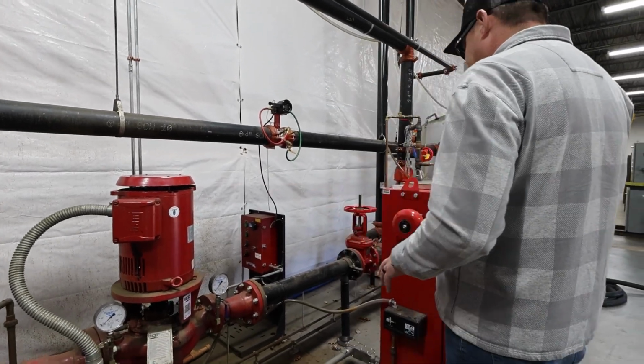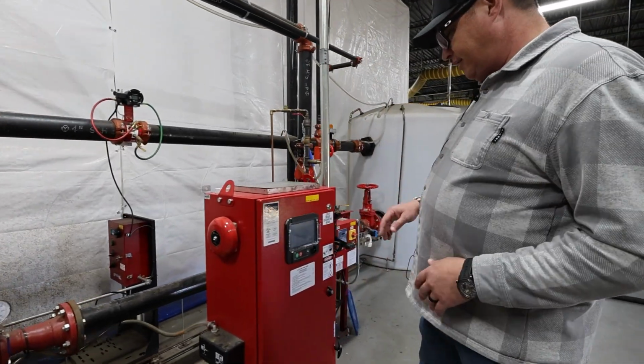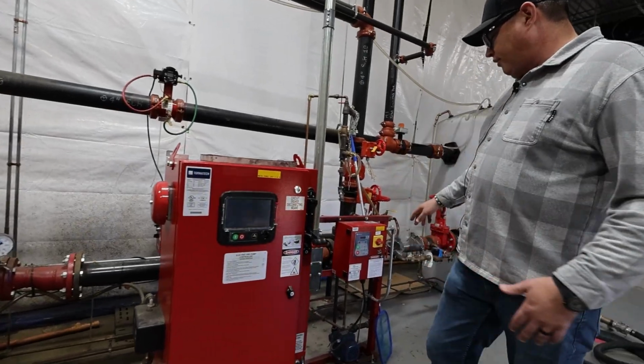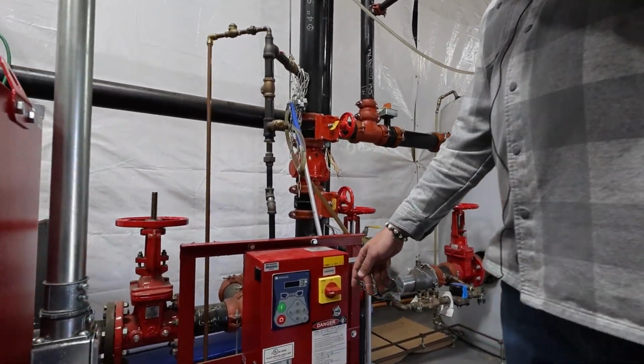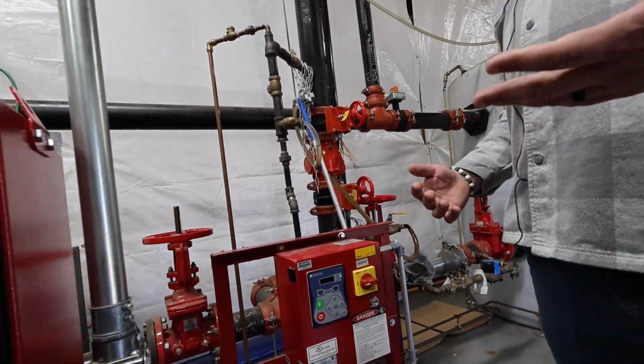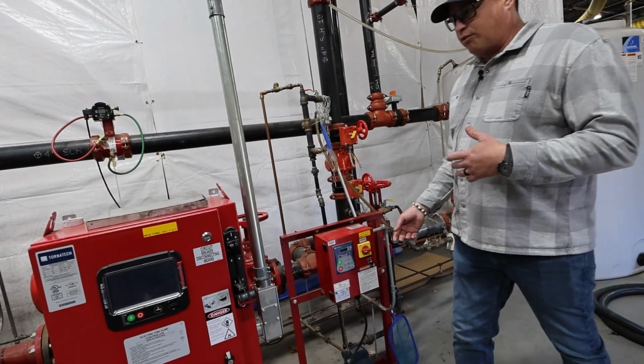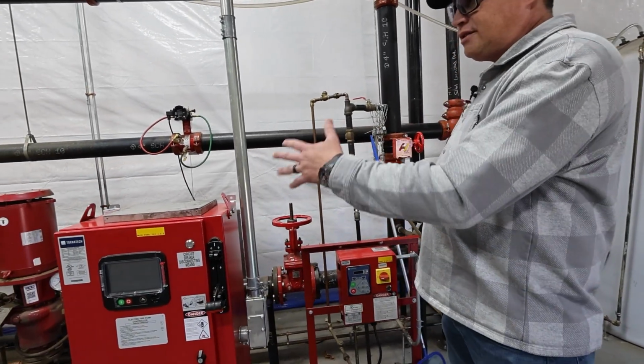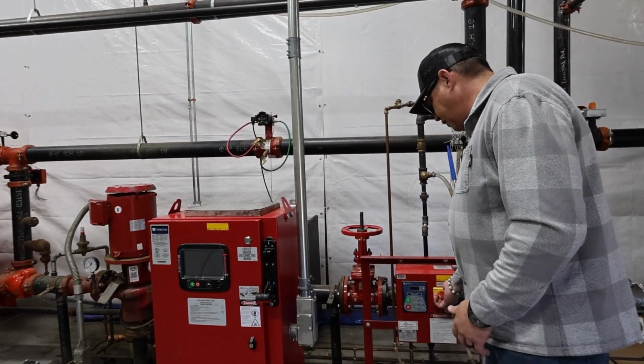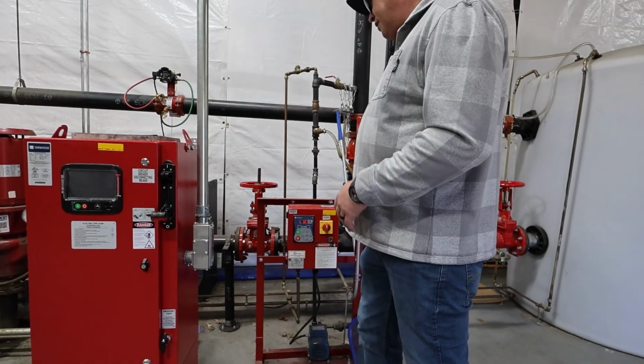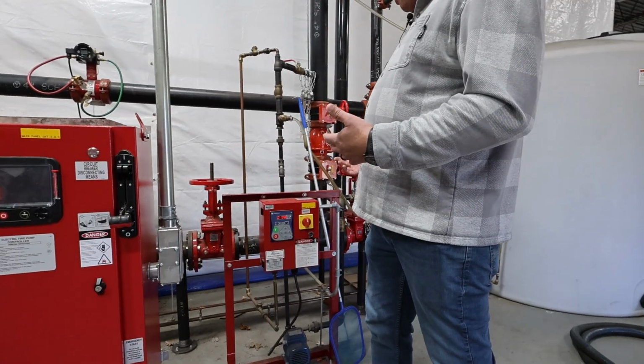So after all that's said and done, we've checked all of our devices and everything. We're gonna check over on our jockey pump. A lot of the time, this equipment's already on because the pump is in service. We're here at General Air, and so this is a training lab. We're gonna turn this on, make sure that our jockey pump is pumping like it should.